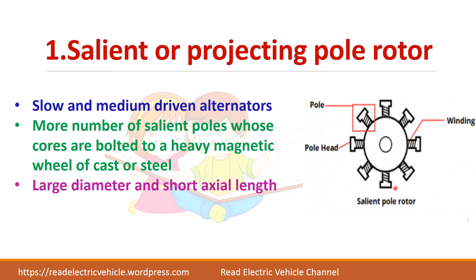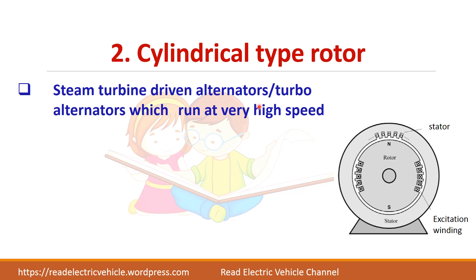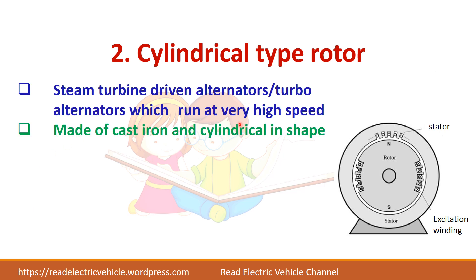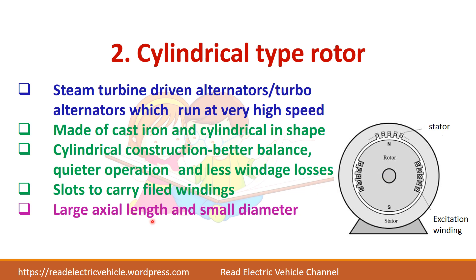Salient pole rotors have a large diameter and short axial length. The cylindrical type rotor is preferred for steam turbine driven alternators which run at very high speed. There is a greater advantage in having the cylindrical structure because they give better balance, quieter operation, and the windage loss will also be less. These rotors are characterized by large axial length and small diameter.